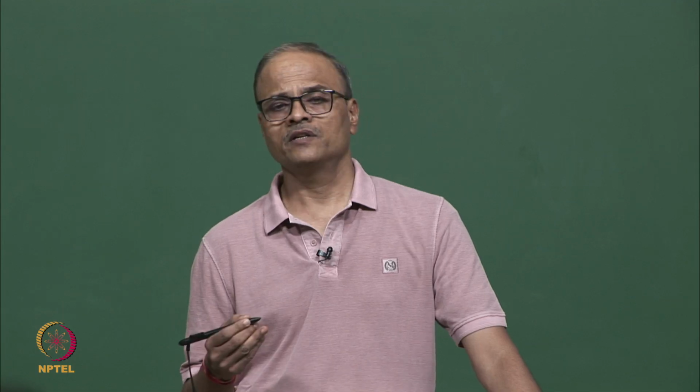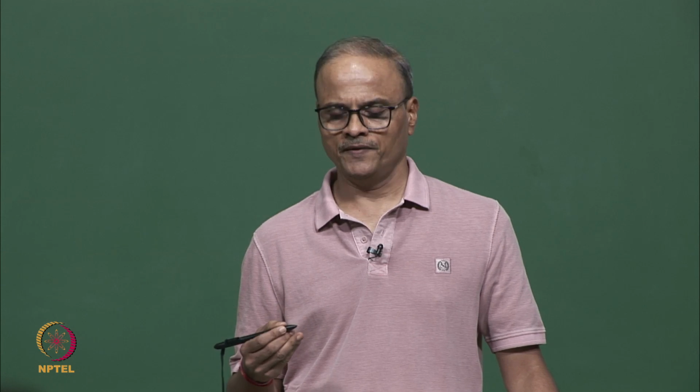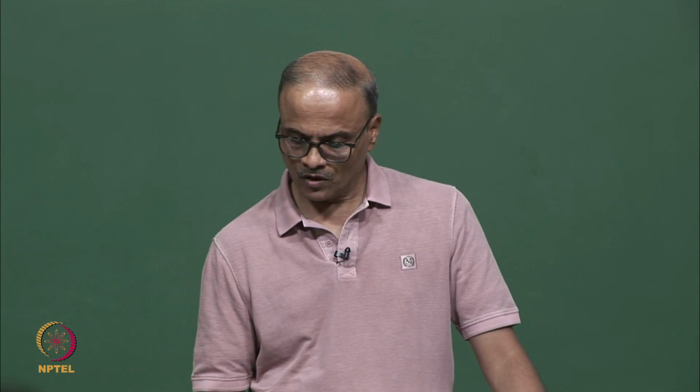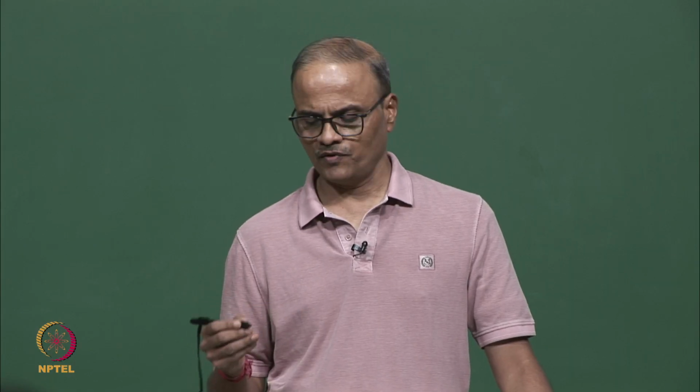That is, the FFT analyzer must have ICP compatible inputs, so that the necessary electric power required for the functioning of these transducers can be supplied; CCLD enabled inputs are required. In that case, we do not require any signal conditioning in between. The output of such transducers can be directly fed to the FFT analyzer.